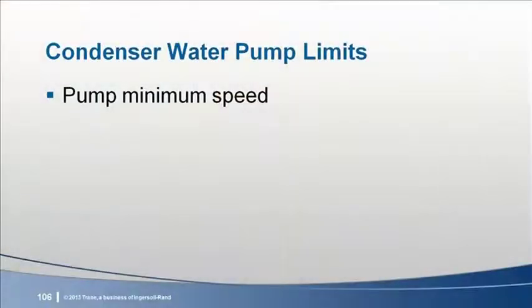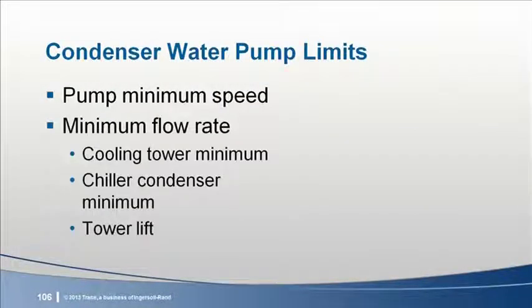The condenser water pump limits either its minimum speed or the highest of three flow rate limits. We already discussed the cooling tower and chiller condenser minimum flow rate limits. A third possible limit is that there will be a speed below which the condenser water pump will no longer be able to overcome the open portion of its loop, that is, from the basin of the cooling tower to the top of the cooling tower. For each application, the minimum flow rate and pump speed must be determined using the highest of these three limits.